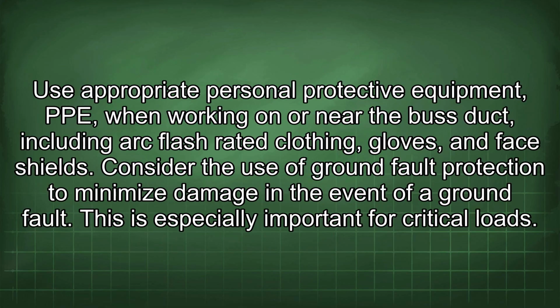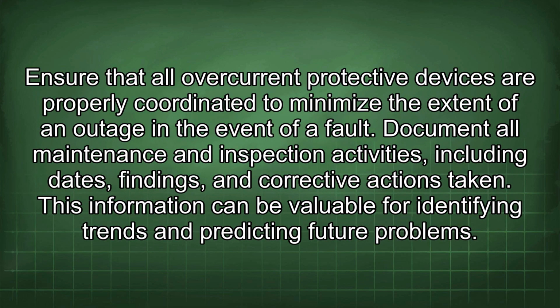Use appropriate personal protective equipment, PPE, when working on or near the bus duct, including arc flash rated clothing, gloves, and face shields. Consider the use of ground fault protection to minimize damage in the event of a ground fault. This is especially important for critical loads. Ensure that all overcurrent protective devices are properly coordinated to minimize the extent of an outage in the event of a fault. Document all maintenance and inspection activities, including dates, findings, and corrective actions taken. This information can be valuable for identifying trends and predicting future problems.